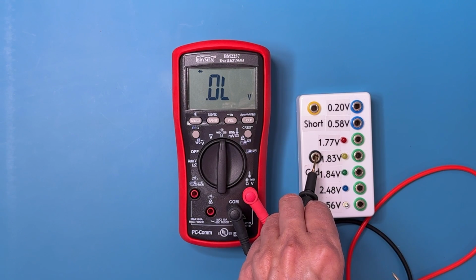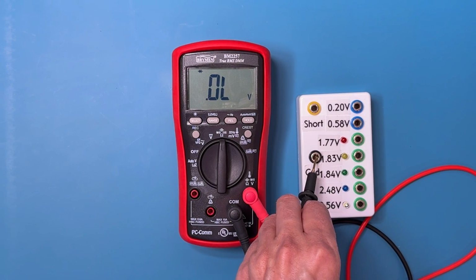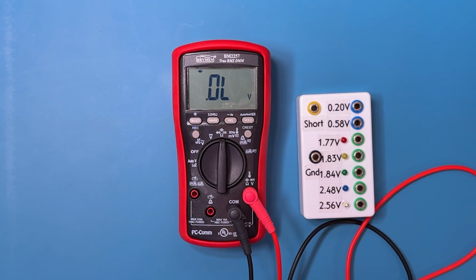Diodes can fail open, meaning they no longer conduct electricity when forward biased, or they can fail closed, meaning that they freely conduct electricity in both directions and act as a short circuit. As you would guess from its name, Diode Check is intended to help test diodes, both regular diodes and light-emitting diodes, for proper operation. In this mode, the multimeter emits a small voltage and detects the voltage drop produced by the diode. For regular diodes, some multimeters will produce an audible signal when a valid forward bias voltage is measured. The audible signal, usually a quick beep, is very helpful as it allows you to stay focused on the components being tested. You don't need to glance at the multimeter while making sure that the probes are still where you intended them to be.